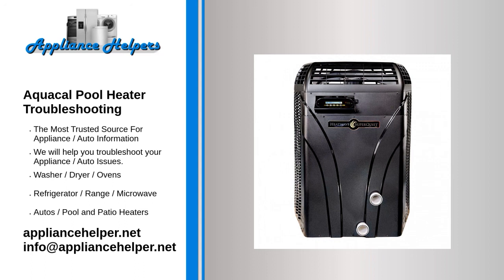Check the filter. If your pool heater is not getting enough water, then this could cause it to be faulty. Pool heaters rely on a steady stream of water in order to operate properly. And when this is interrupted, you will start to run into issues. To make sure that your pool heater is getting enough water, you need to check your filter.